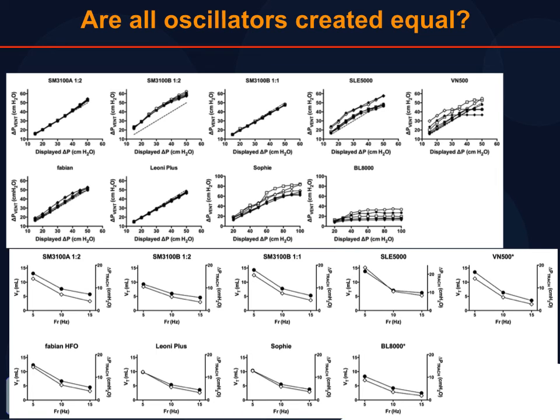And we noticed that most of the devices were able to generate, when you dialed up a pressure, that pressure. There was a linear relationship. And there's a lot of little graphs here. It's easy to see on this one. They reflect different ET tube sizes, a 2.5, a 3 and a 3.5, so different resistances, and then the 3 different frequencies, 5, 10 and 15 that we chose. And we've been criticised for picking those frequencies in this paper by some of the reviewers, but they were just pragmatically chosen to show the upper and lower range and then the middle range. And we saw a fairly linear relationship that occurred.